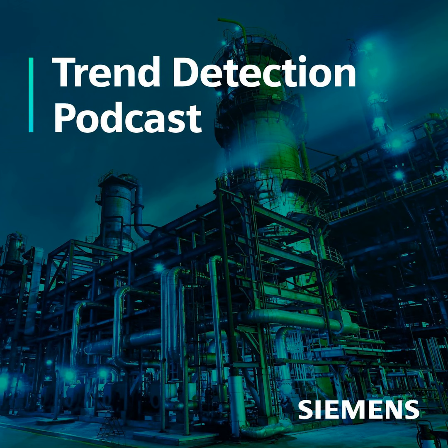Yes, so we have the different assets within the machine, and that is really down to the different functions of core sections of the machine and how they operate. One example is the solder bath, which is the pool of molten solder that's then pushed up into a wave. That has a set of attributes and parameters associated with it, but then we also have a separate one for the conveyor. And the point you made to me at the time was that if we segment these out into different key blocks, we can monitor them separately. That means the alert you're getting is also more specific. So you're not getting alerts saying there's something wrong with the wave solder system. Yeah, which is like, okay, well, what's wrong then? Lots more investigation required. It's a bit like saying there's something wrong with your ship.